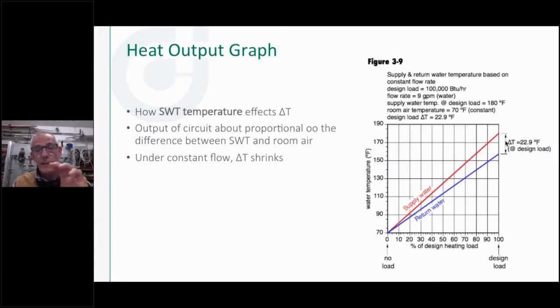Think of that fin tube heat emitter: the air coming in starts out at, say, 60 degrees at my design condition, and as it warms up, I've got less delta T between the air temperature and the temperature of the fin at, say, 170 degrees, whatever it might be. My delta T starts closing up. Eventually my thermostat satisfies and shuts off, so it's really the thermostat that's in charge of what's going on in there. But this is what would happen if you just sat there and measured the delta T going out to that circuit and coming back.